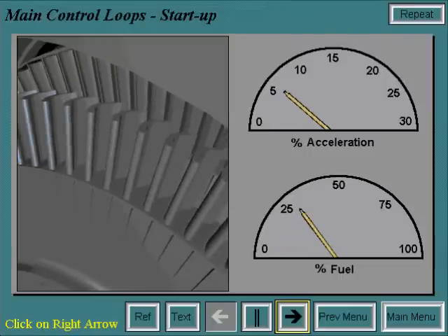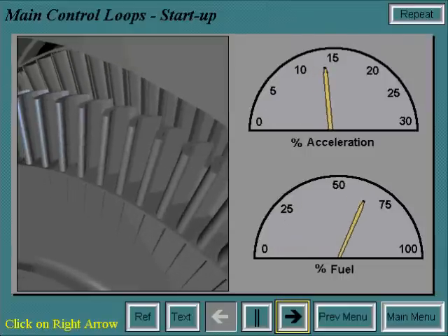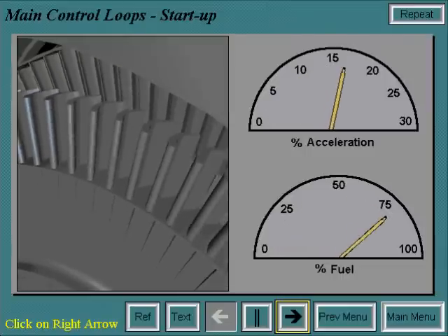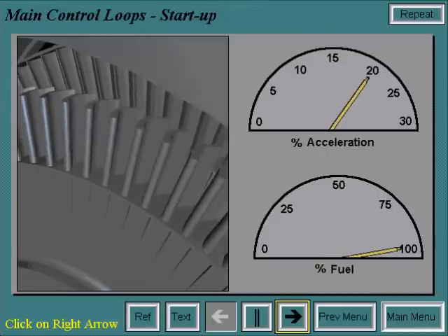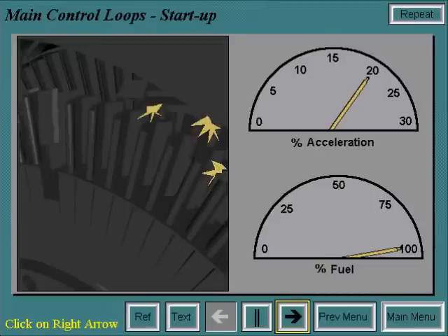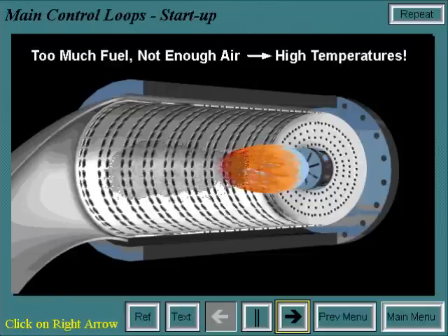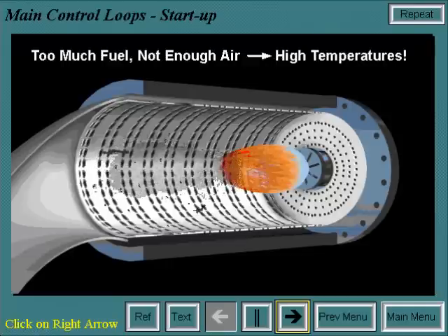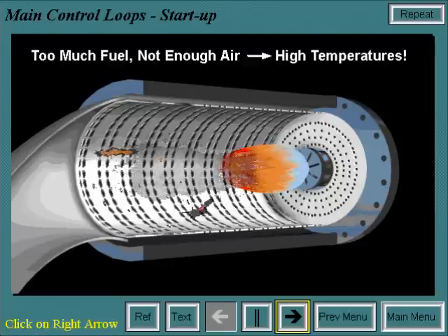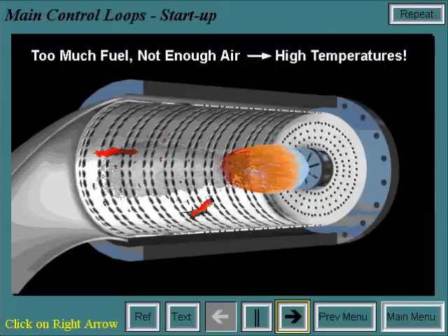Acceleration of the turbine rotor must be controlled so as not to exceed the allowable forces on the rotor. Exceeding the limit can cause heavy damage to the rotor. During start-up, the airflow rates are low. If there is too much fuel added to the combustors while there isn't enough air, temperatures could get dangerously high, potentially damaging internal hardware.